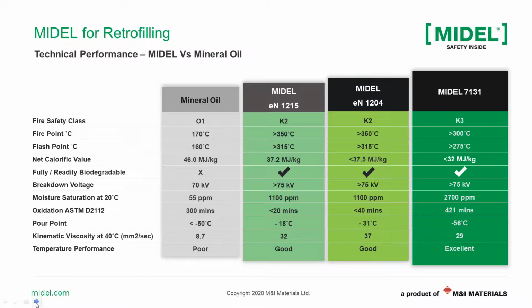Steve mentioned something about the oxidation stability, and in this case, if you just compare the numbers to each other, you can see that the MIDEL EN natural esters have a lower number on this comparison, whereas mineral oil and MIDEL 7131 have higher numbers, and the higher number means the better oxidation stability, which could lead us to say that natural esters are not always suitable for use in free-breathing transformers. That is why we always recommend using them in a sealed condition. MIDEL 7131 and the synthetic ester you can use in both sealed or free-breathing construction as well.